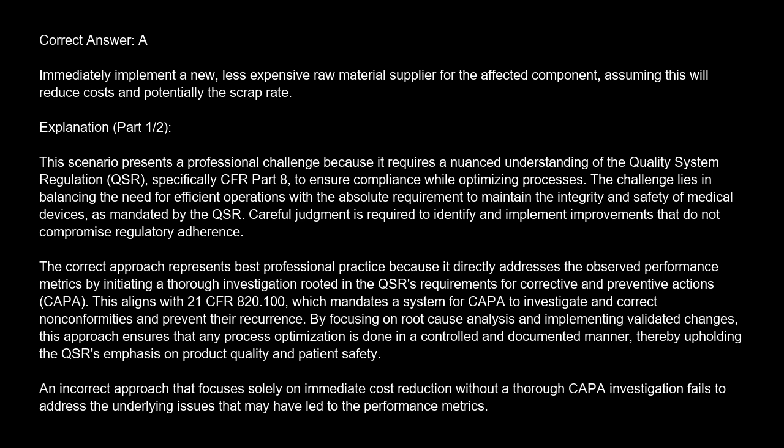The correct approach represents best professional practice because it directly addresses the observed performance metrics by initiating a thorough investigation rooted in the QSR's requirements for corrective and preventive actions, CAPA. This aligns with 21 CFR 820.100, which mandates a system for CAPA to investigate and correct nonconformities and prevent their recurrence. By focusing on root cause analysis and implementing validated changes, this approach ensures that any process optimization is done in a controlled and documented manner, thereby upholding the QSR's emphasis on product quality and patient safety.